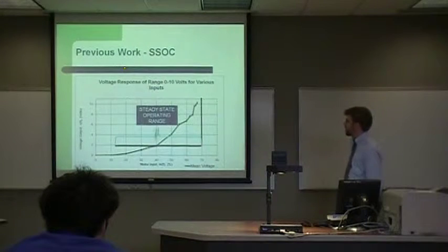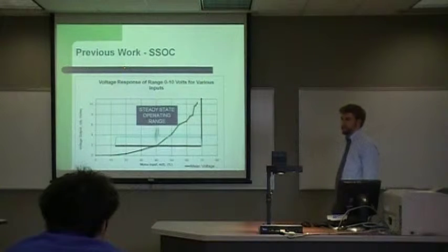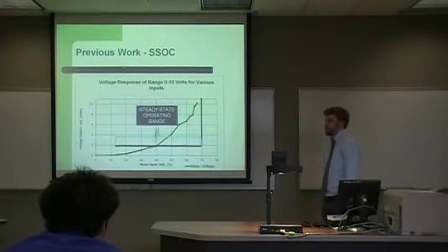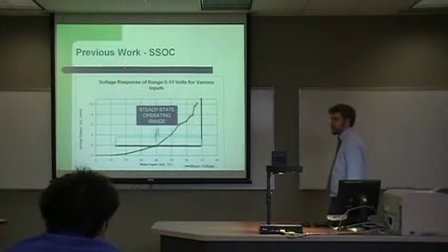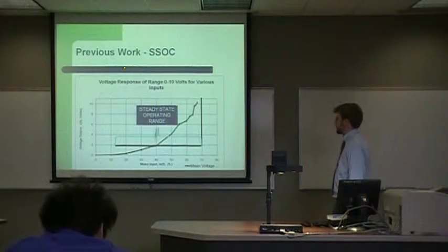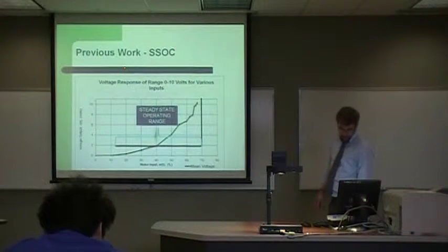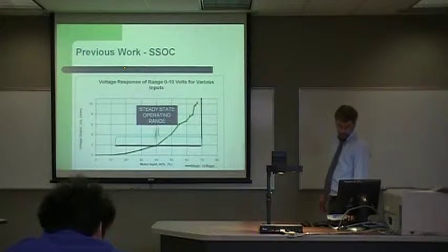Well, our operating range is actually between about 12% to 67%. Below 12%, there's a lot of oscillation, there's a lot of noise, and it produces quite an interesting set of data. So it's hard to use that data. So we use our operating range between about 12% to 67% or so to get the 0 to 10 volts.